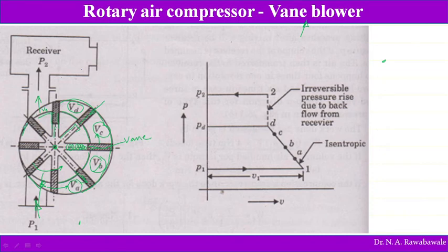no clearance. That means this air is completely squeezed out, no air will come here, and there is zero clearance. Again, when this vane comes here, suddenly it starts to come out, and the space is provided. Again, this space captures fresh air and forces it in the forward direction. Then it comes to Va, Vb, Vc, Vd, Ve, and from Ve it is squeezed out into the reservoir.